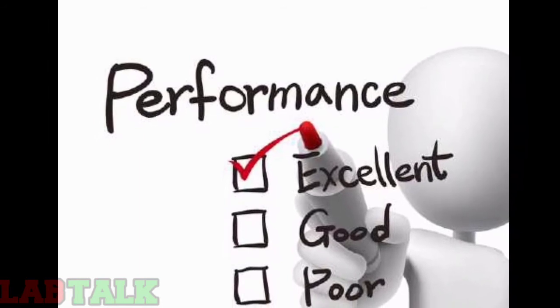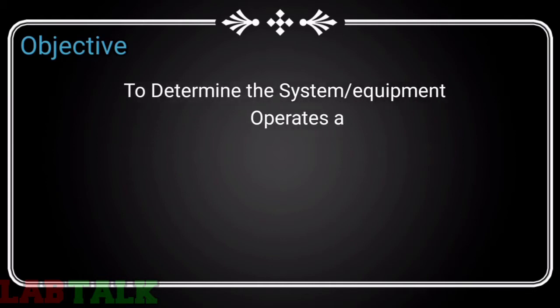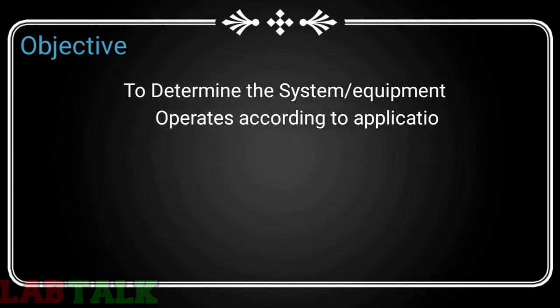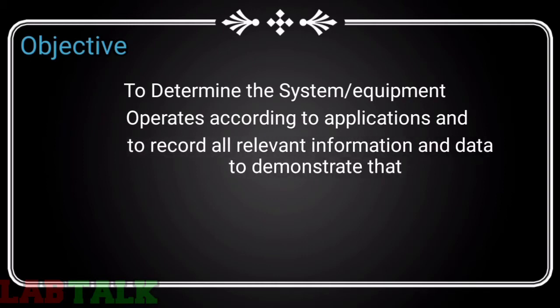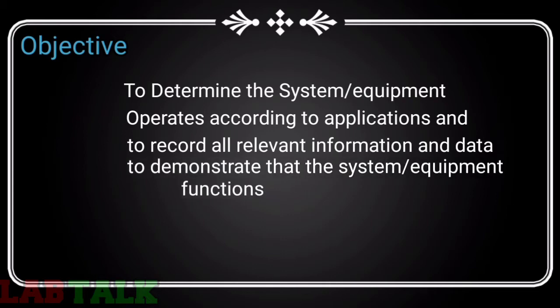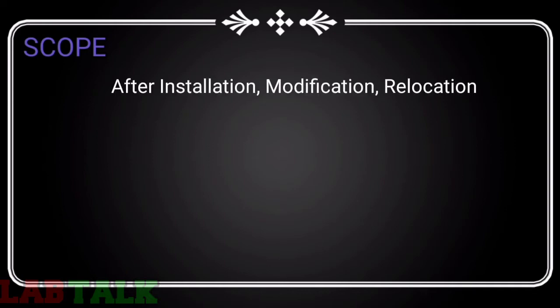Now we will see how to perform OQ and what should be included in it. The objective is to determine that the system or equipment operates according to specification and to record all relevant information and data to demonstrate the system functions as expected. The scope is to perform OQ after installation, modification, or relocation, and after installation qualification has been completed.